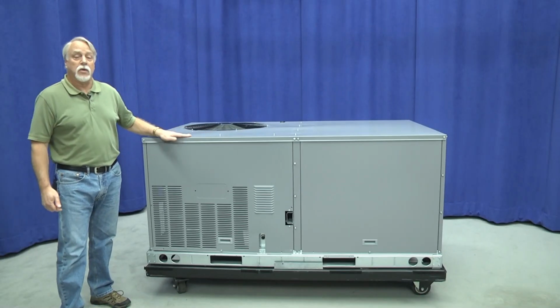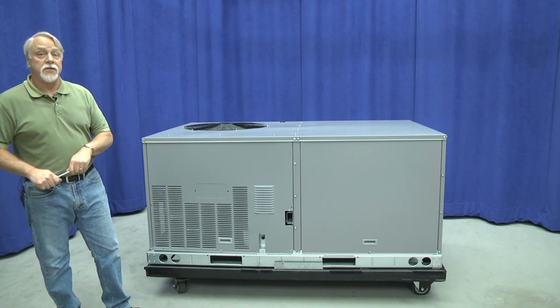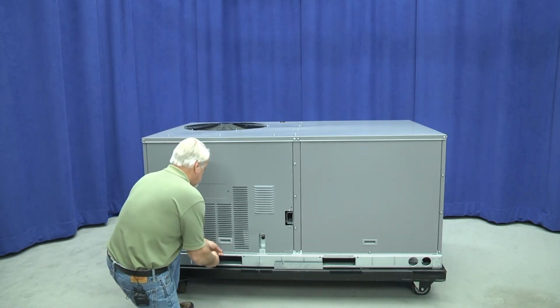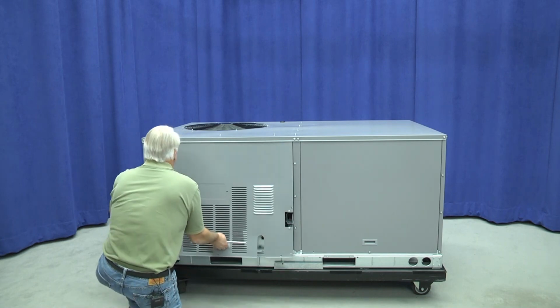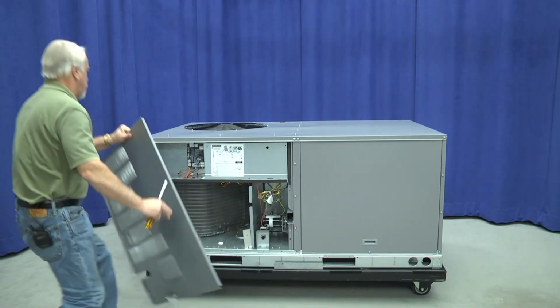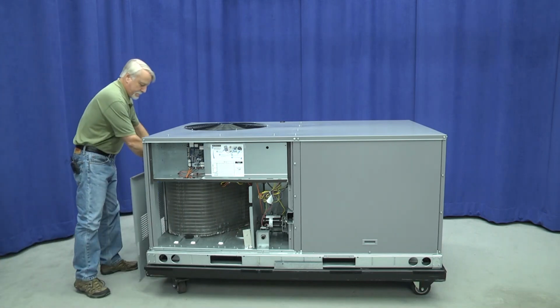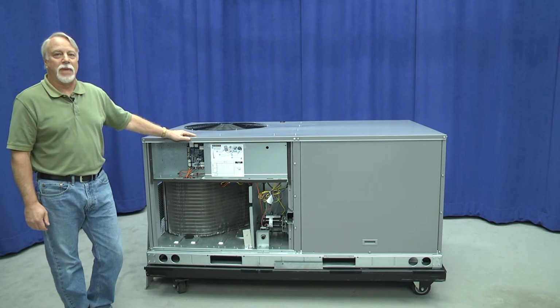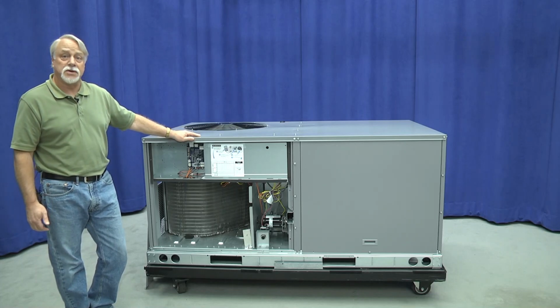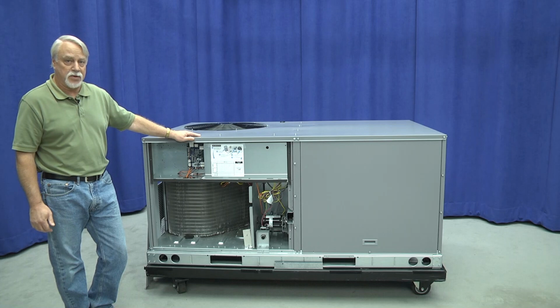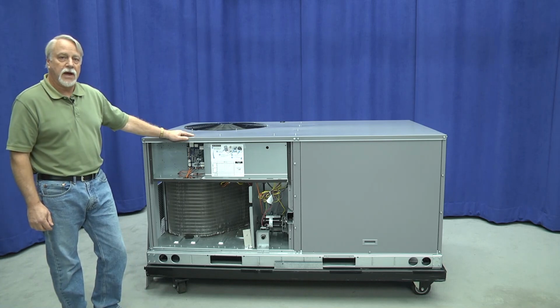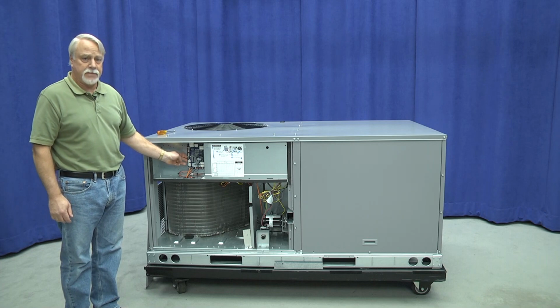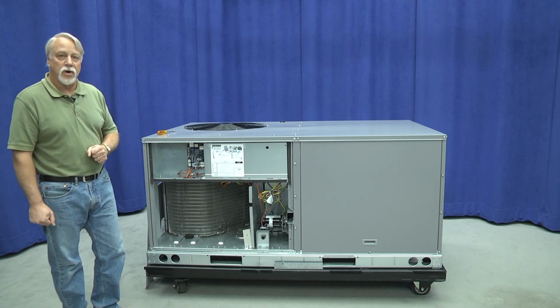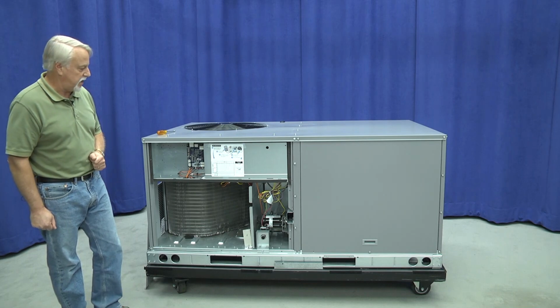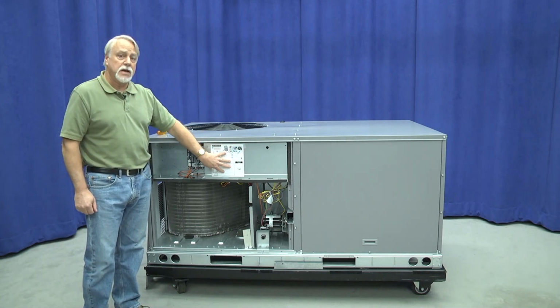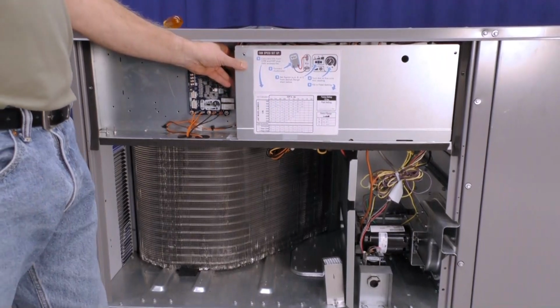We've turned the unit around. Now we're going to remove the outer panels and see what's different. With the control box access panel removed, we can see what looks remarkably the same with this small rooftop unit. The changes that we're going to talk about are specifically with how I adjust the fan and the changes to the control terminal board, which is different with this type of indoor fan assembly. Additionally, notice that there is a sticker that guides us through setting up the airflow levels for the indoor fan.